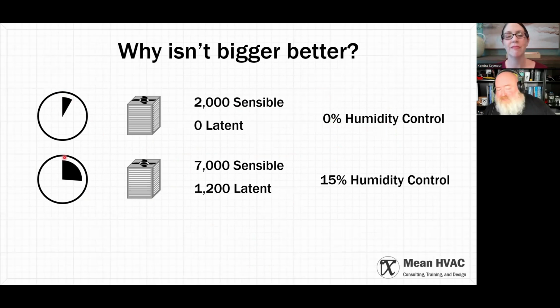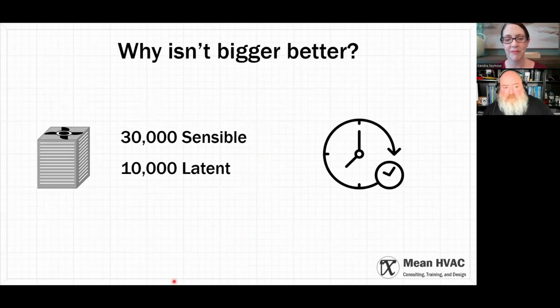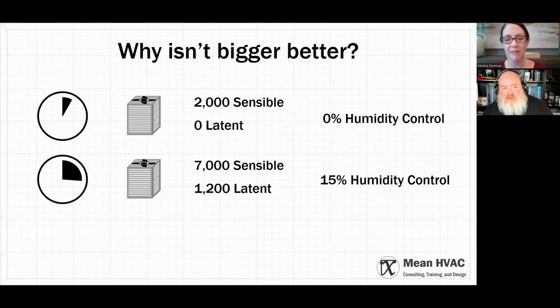Right? And the next five minutes, maybe it's 15% humidity control. And eventually it actually gets higher than that, the 25% total, because it often is making up some loss on the back nine, right? On the back half hour. And so we actually very rarely know how bad it gets when a system short cycles...